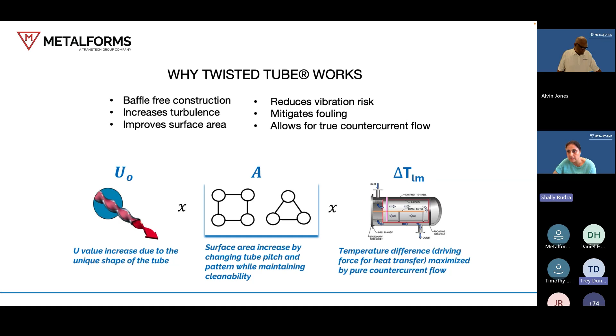Due to the shape of the tube itself, it introduces turbulence in the tube side fluid, thereby affecting the U value or the heat transfer coefficient. And finally, in terms of the delta T or the LMTD, in this particular situation and in several others, we have a possibility with our Twisted Tube technology to convert an existing E shell to an F without making any modifications on the outside, so the nozzles stay in the same location. In this particular case study, we actually impacted all three parameters, and that led to the success of the solution.